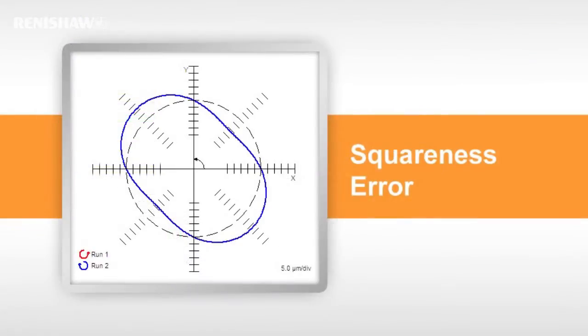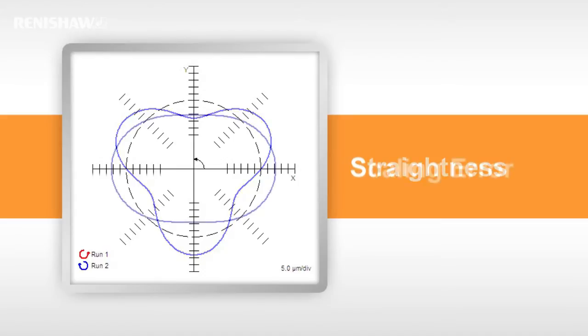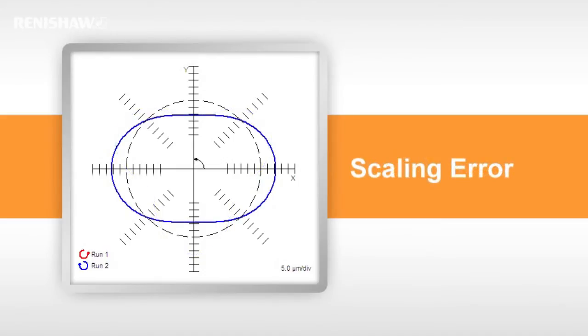This is what a squareness error looks like, an oval shape aligned to either the 45 or 135 degree diagonal. Straightness typically appears as a three-lobed plot. Scaling error, an oval shape aligned to the axes, clearly showing that one axis is moving further than the other.